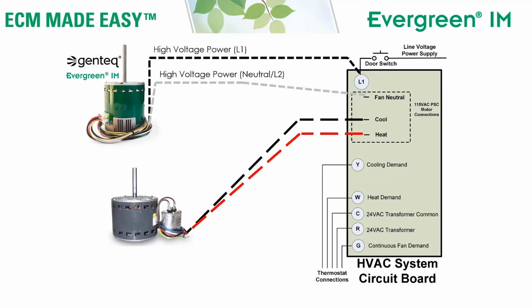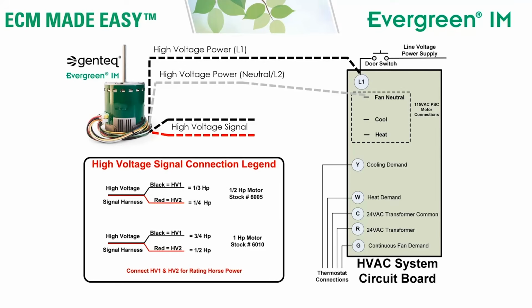All right, with those two new wires connected, we're then going to remove the PSC motor speed wires and remove the PSC motor, and bring out what we call the high voltage signal wires, or what I like to call the horsepower wires, because these wires are used to select the horsepower that the motor is going to operate at. If I connect the red wire to heat or cool and the black wire to heat or cool, and then in the parts bag take a jumper and jumper them together, by energizing both red and black at the same time, I'm running the Evergreen IM motor at its maximum rated horsepower. So the half horsepower motor runs at 1/2 and the 1 horsepower motor runs at 1 horsepower.